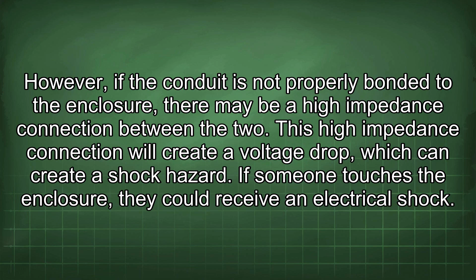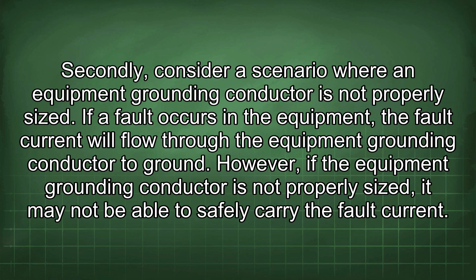Secondly, consider a scenario where an equipment grounding conductor is not properly sized. If a fault occurs in the equipment, the fault current will flow through the equipment grounding conductor to ground. However, if the equipment grounding conductor is not properly sized, it may not be able to safely carry the fault current. This can cause the equipment grounding conductor to overheat and potentially melt, which can create a fire hazard.